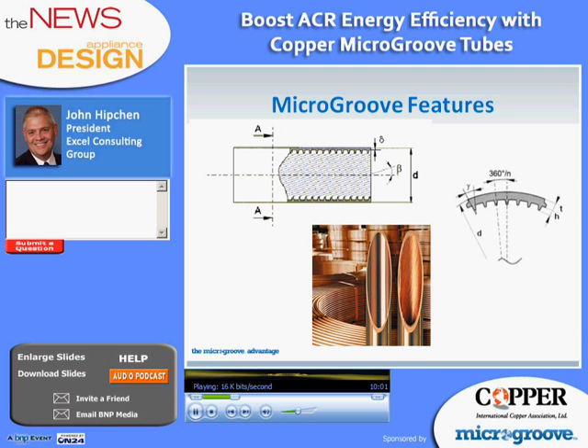MicroGroove tubes have internal enhancements to reduce the formation of boundary layers. These enhancements are grooves and proprietary patterns the tube manufacturers put on the inside tube wall. The exact configuration of the internal grooves and patterns is based on a long history of technical development and design, and is backed up by both experimental and field performance data. And the data clearly shows significant advantages with MicroGroove tubes. And this next slide shows why.